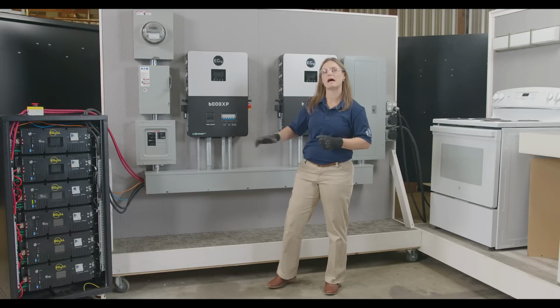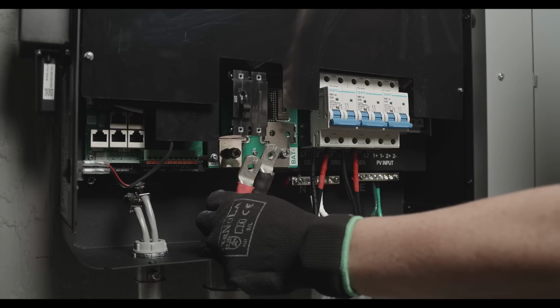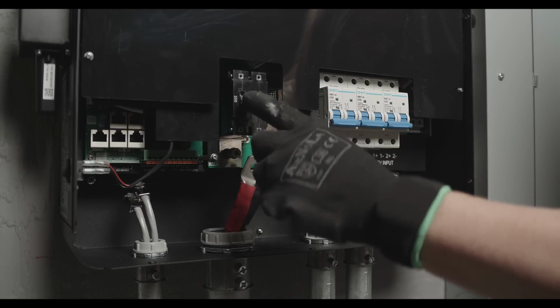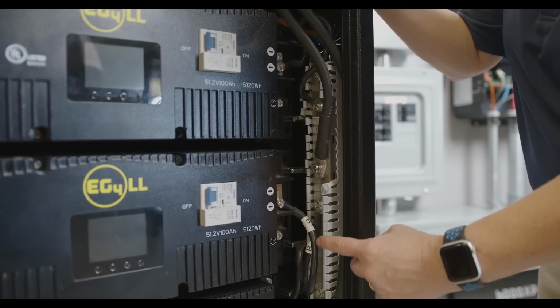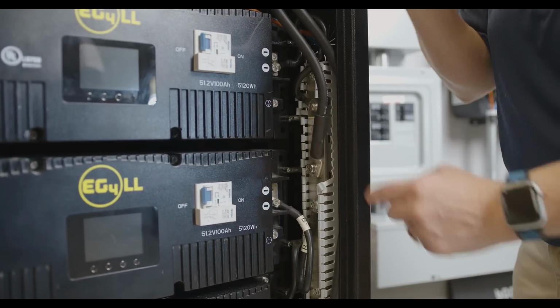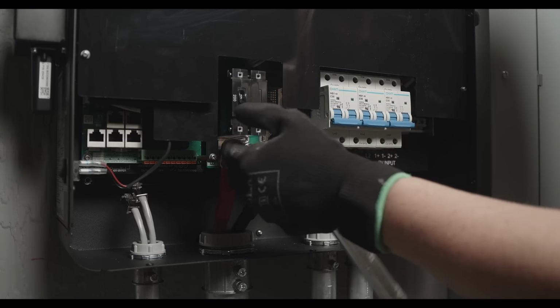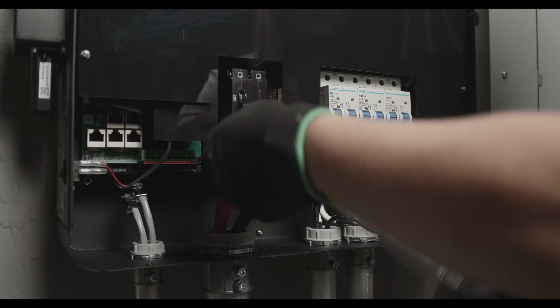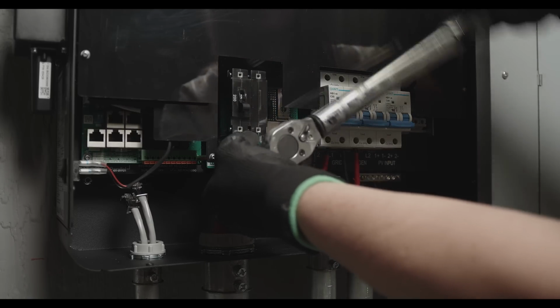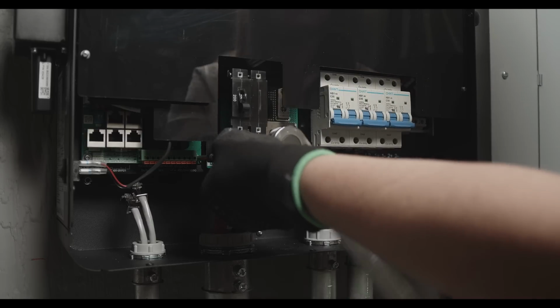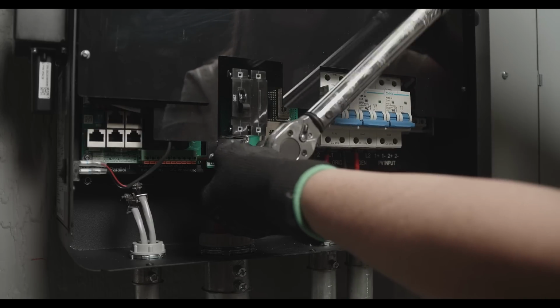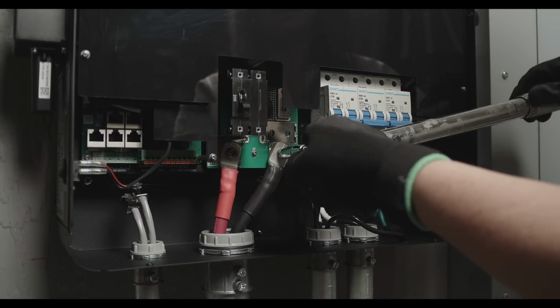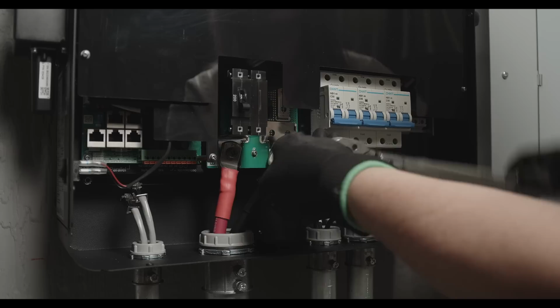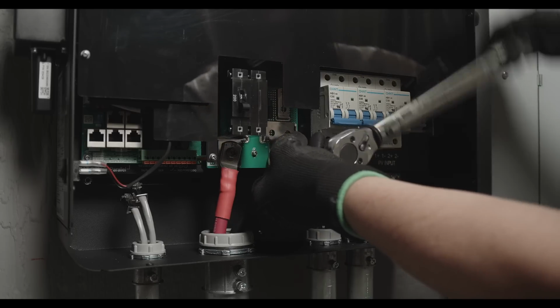Now let's connect the battery cables. Make sure all breakers are in the off position and that there's no voltage. If using a battery rack, double check all connections. Attach the red cable to the battery positive terminal and black cable to the battery negative terminal. Tighten the screws to 36 to 45 inch-pounds or 4 to 5 Newton meters. Be advised that the recommended battery capacity is more than 200 amp hours.